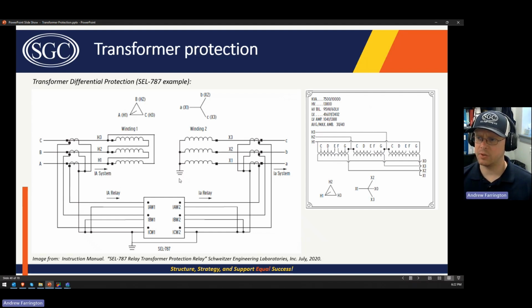The other one is that there is a ground source within the zone of protection. And what do I mean by that? This is a Y winding that is solidly grounded. So if we have a single line to ground fault out here beyond these CTs, there's going to be zero sequence fault current provided to that fault. And we talked about how the zero sequence fault current circulates in the delta side, and that the transformer is actually acting as a source of zero sequence fault current and not a path through which it can flow. So it's originating here in that delta winding and then being sourced through the Y winding's neutral connection to the fault. So this CT is seeing that zero sequence fault current, but these CTs do not see it, because it's circulating here in the delta and isn't measured by these CTs.